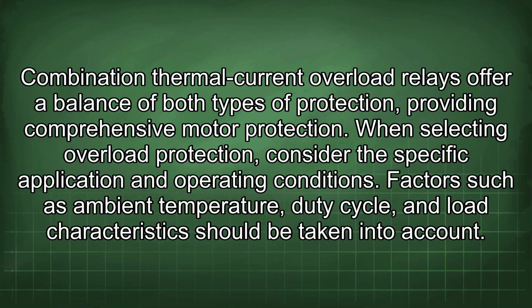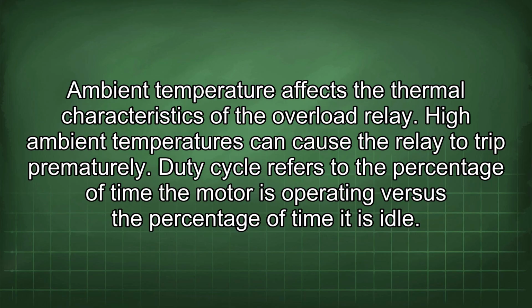When selecting overload protection, consider the specific application and operating conditions. Factors such as ambient temperature, duty cycle, and load characteristics should be taken into account. Ambient temperature affects the thermal characteristics of the overload relay. High ambient temperatures can cause the relay to trip prematurely.